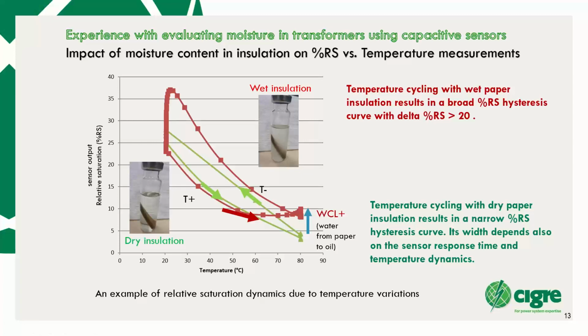What happens if we cool down now? The whole water, which is already in the oil and dissolved in the oil, goes back and tries to go into the solid insulation. However, when the oil is cooled down, the solubility of moisture is decreasing. That means that the relative amount of moisture in oil increases. We see here on the photo how the oil is getting turbid. And this is the most dangerous point. In such a case, of course, we will have a very low breakdown voltage, which will immediately lead to breakdown.